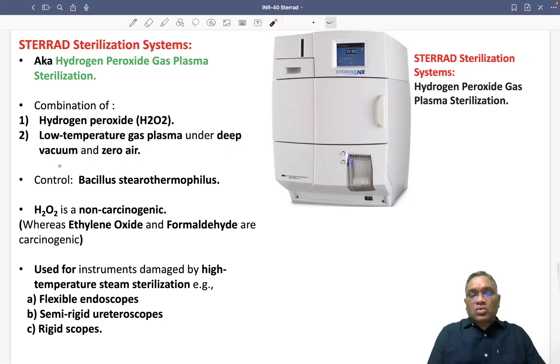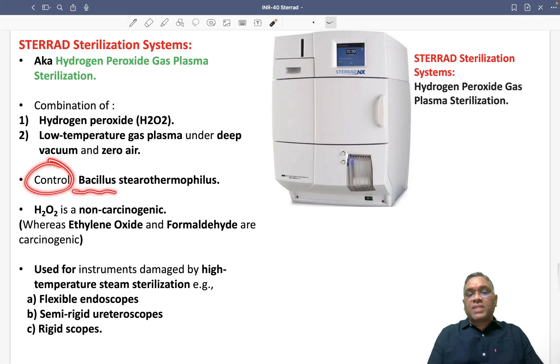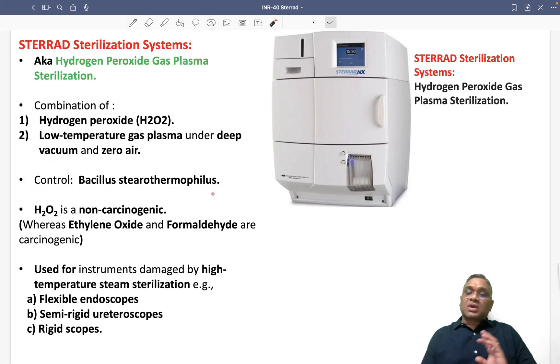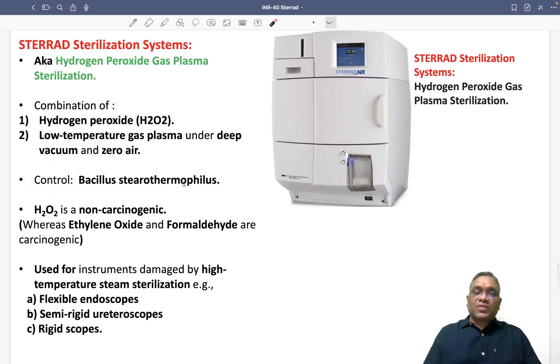So what is the control used in the Sterrad System? That is Bacillus stearothermophilus. Bacillus stearothermophilus is used as the biological control.